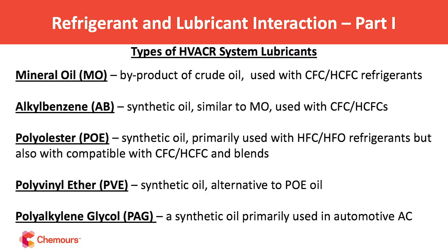Let me start by talking about the different types of refrigerant oils. A lot of them go by acronyms. Starting with mineral oil, which has been the workhorse for decades — sourced from petroleum feedstocks and used extensively with CFC and HCFC refrigerants. Alkyl benzenes are a synthetic version of mineral oil, also used extensively with CFCs and HCFCs. As we moved into HFC-generation refrigerants, we had to change lubricant type and transitioned to what is known as POEs, or polyol esters — a very important class of lubricants.